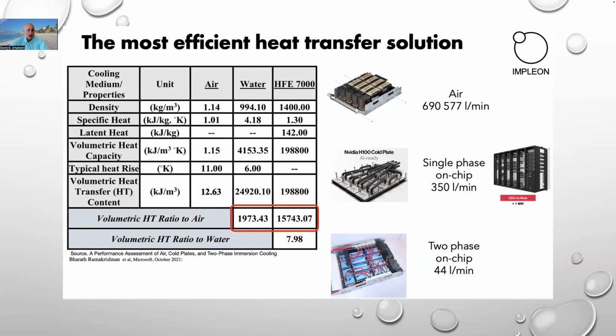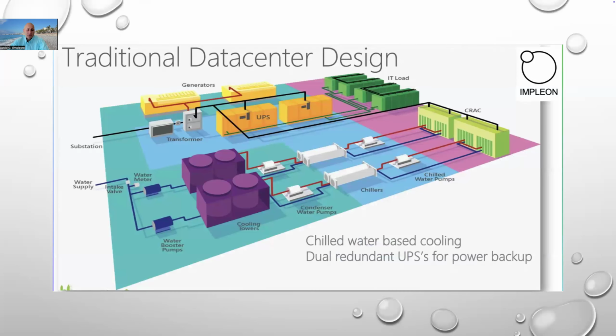Also, you should think about how to take out the energy, the heat, and you can compare air performance, water-based liquid cooling solutions, and two-phase on-chip cooling. When we have AI dedicated racks, we have a huge flow, like 350 liters per minute, and in that case, we need a row-level CDU, which will cover all the racks, and we will not spend space on CDUs because we have this big flow rate. It would take too much space. And if we shift to two-phase, then we can have rack level CDUs, and also we can simplify the data center design itself.